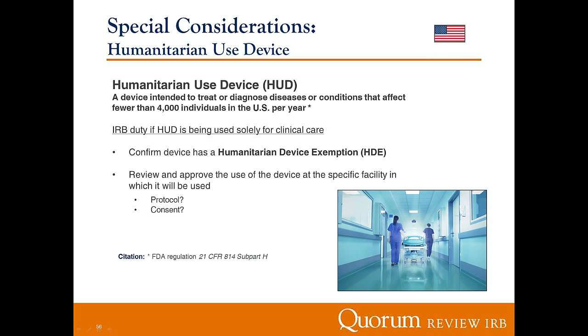Next, humanitarian use devices. These are devices intended to treat or diagnose diseases or conditions that affect fewer than 4,000 individuals in the U.S. per year. Here, I'm only talking about the U.S. These are interesting. HUDs are essentially devices meant to be used for clinical care, but they don't quite have the efficacy requirements that another device would have that's being marketed to many people and going through the pre-market approval process. Because it doesn't have as many efficacy requirements, the FDA decided that it wants some additional oversight over these devices.